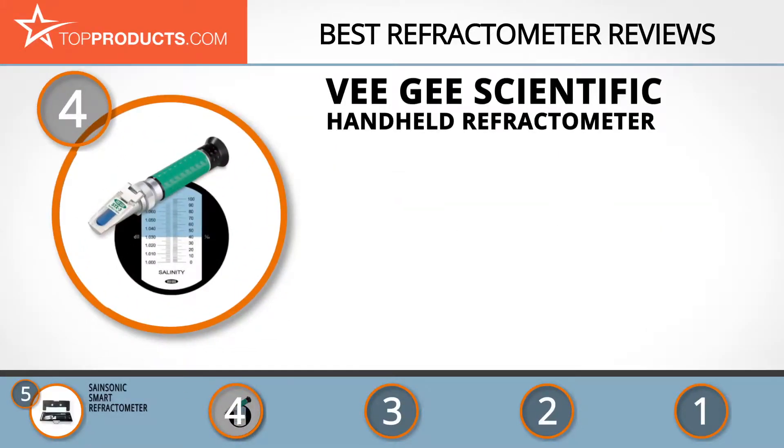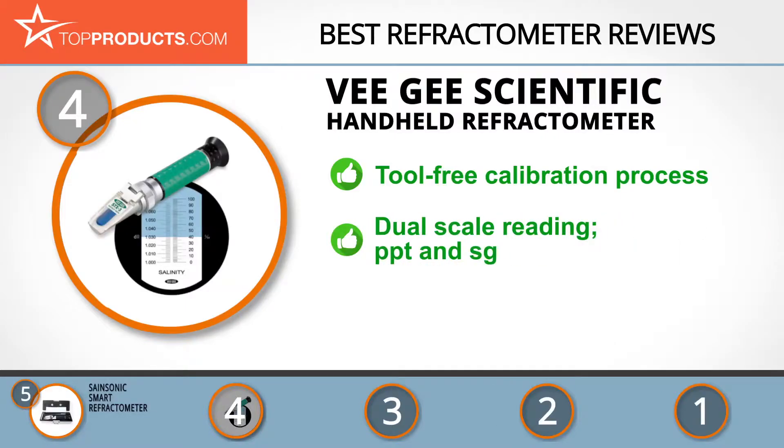Next on our list at number four is the Vee Gee Scientific Handheld Refractometer. Vee Gee Scientific sells high quality products including those imported from its overseas factories through its global dealers network. The Vee Gee Scientific Handheld Refractometer is constructed with a durable metal body, calibrated using a tool-free patented calibration ring and a set screw. Its optical glass prism is mounted in all-metal housing for quick temperature equilibrium.